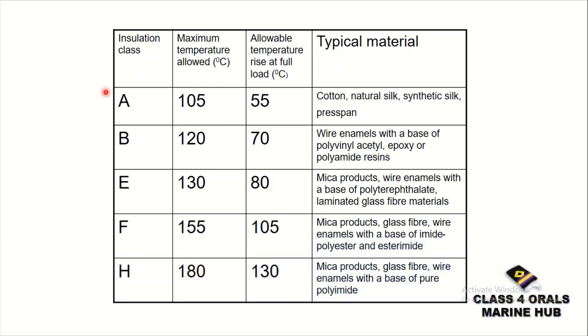Starting with Class A insulation: the maximum temperature allowed is 105 degrees centigrade, and at full load the allowable temperature rise is 55 degrees. The typical materials are cotton, natural silk, synthetic silk, and press pan.